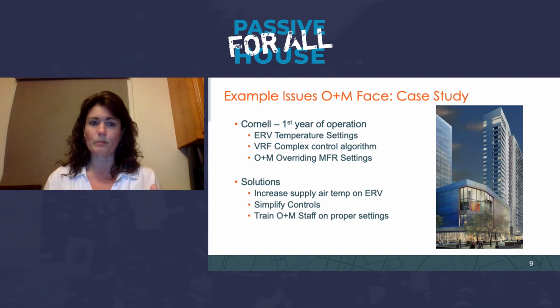It took a couple months or so, but we bumped up the ERV supply temperature to a point where there were no complaints anymore, 70 to 72 degrees. We simplified the controls on the VRF. So really, there had to be a strong demand from one or the other for the system to switch over.